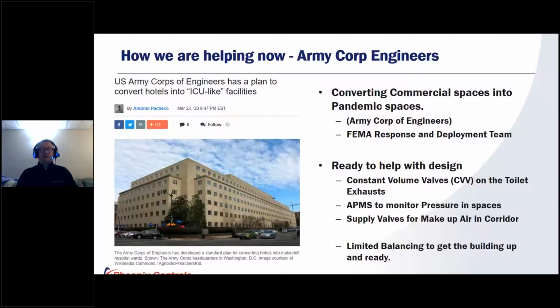And then obviously supply fans and supply valves to that corridor to compensate for the makeup air for that negative draw, right, that's coming out through those toilet exhausts. The benefit here is that there's limited balancing. You can get the building up and running quickly, and you can provide good, stable, dependable directional flow, right? And so that's something that we can certainly do in the short term. But like I said, for the other applications, that's a much more integrated design for the hospital.